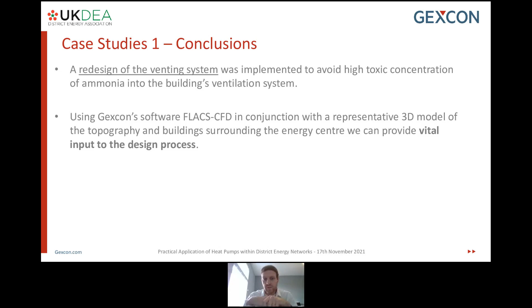The second case study I'm going to briefly talk about is more of an overall consequence modeling study that includes not only the release or dispersion modeling part of the consequence assessment, but also gas detection and/or explosion modeling. Many heat pump installations do include gas detection that is interlocked with isolation in order to mitigate an ongoing release resulting in the accumulation of gas, which could be ignited by the flammable material in a closed environment.